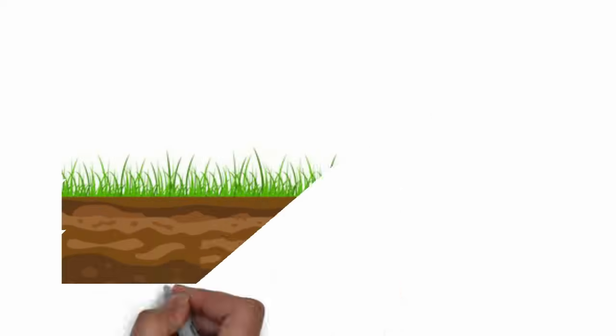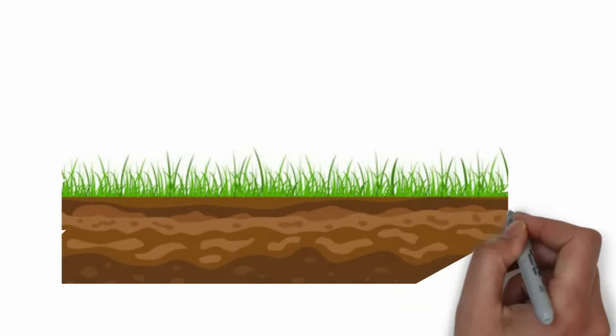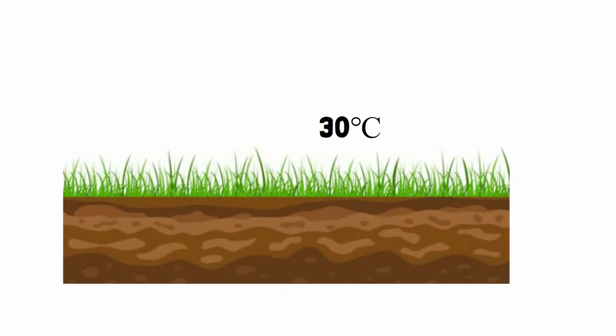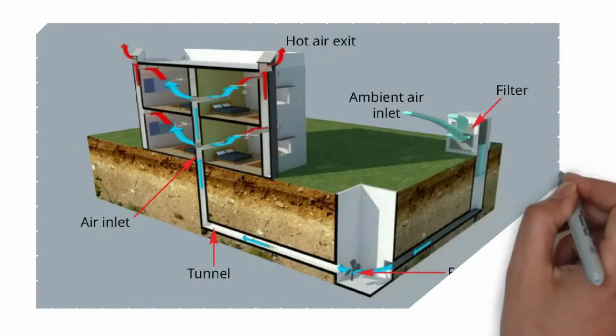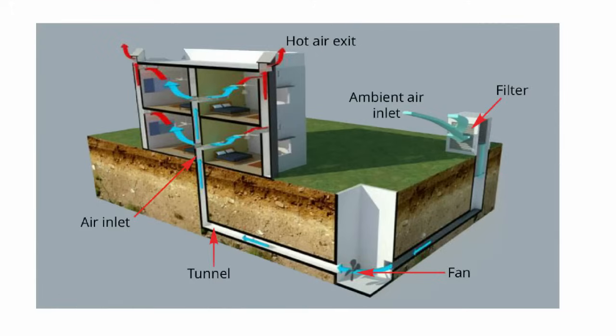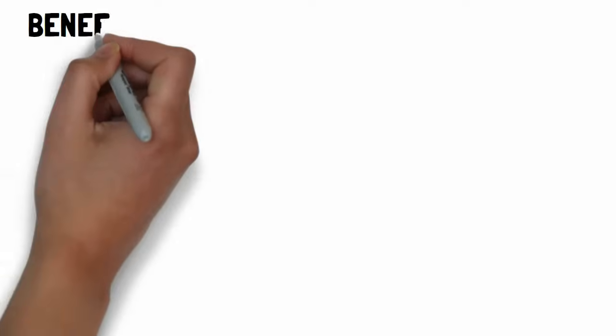The temperature below the earth is constant throughout the year. By comparing air temperature and ground temperature, the difference is a minimum of 2 to 6 degrees Celsius. Using this principle, the Earth Air Tunnel is used for preheating and cooling, which consists of a network of pipes buried at a reasonable depth below the ground.